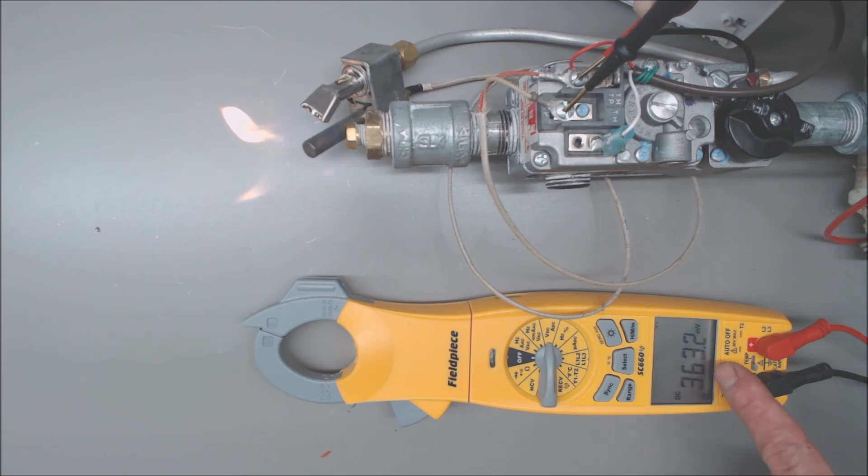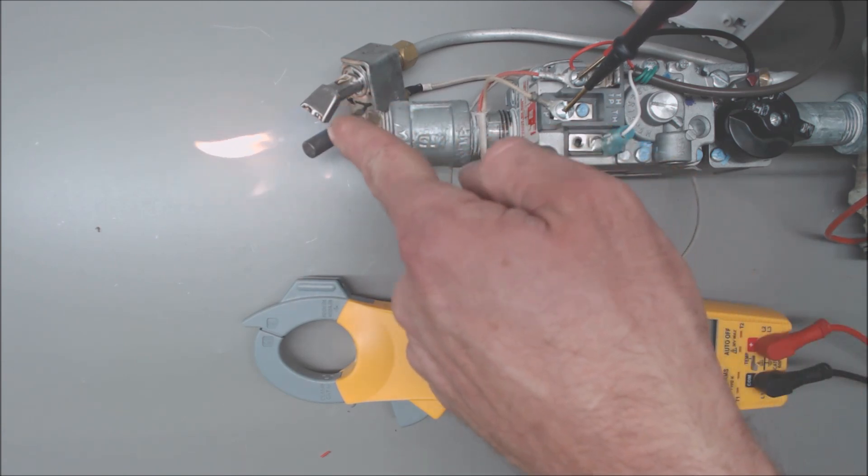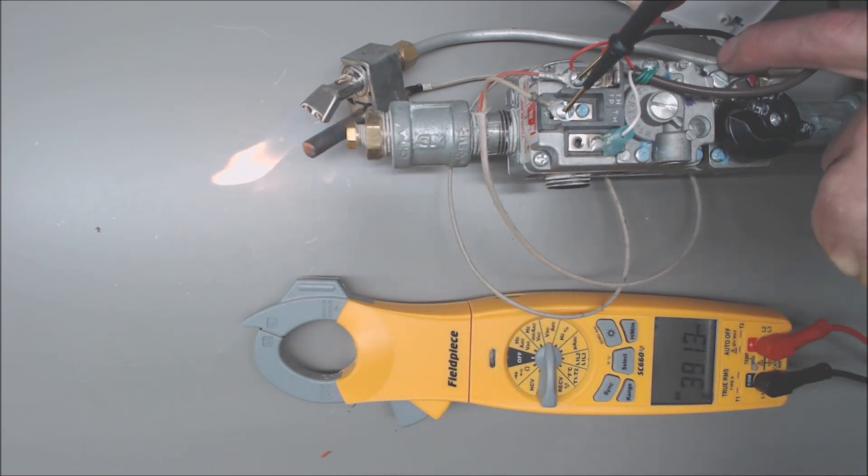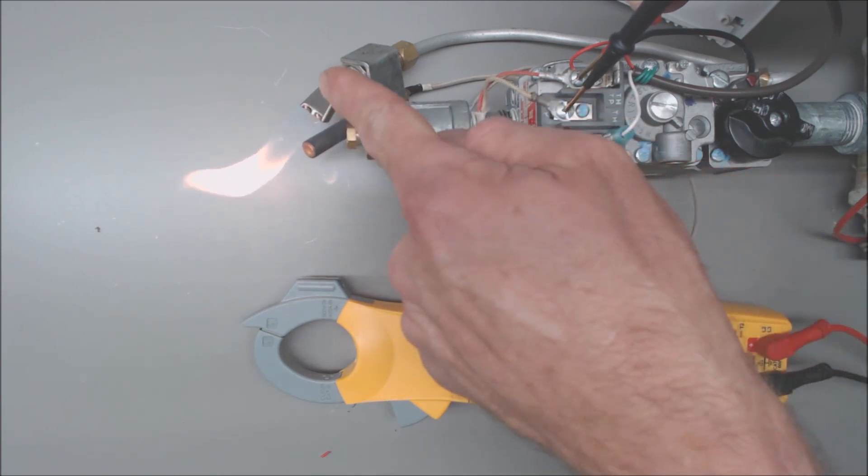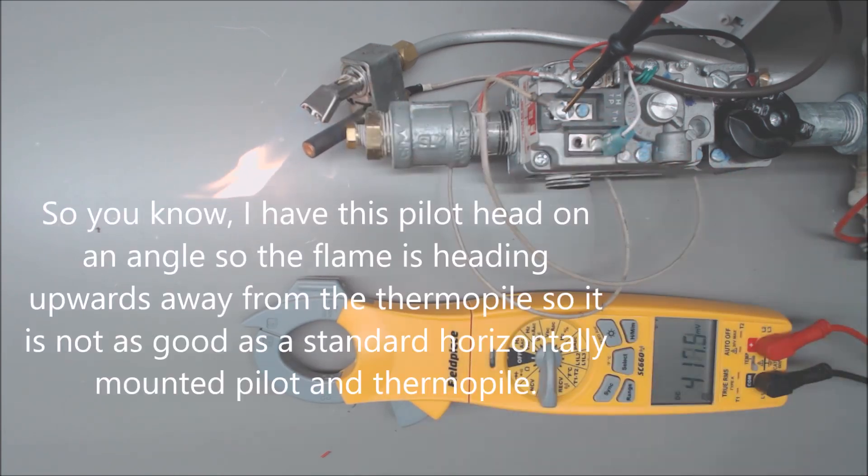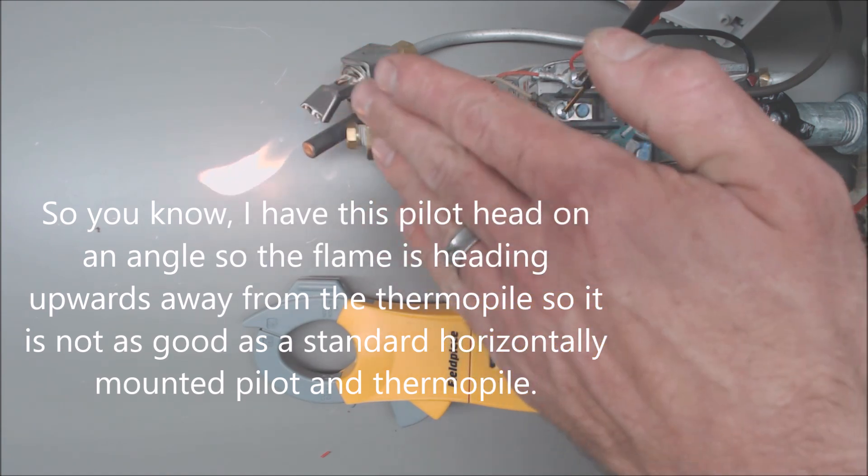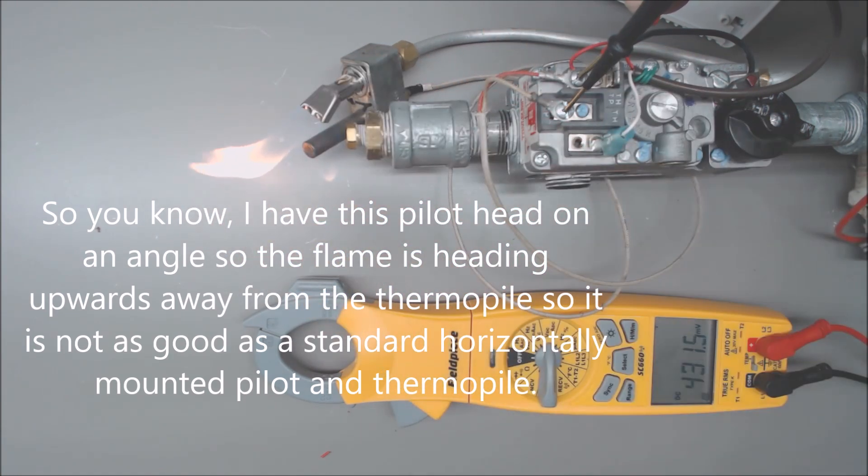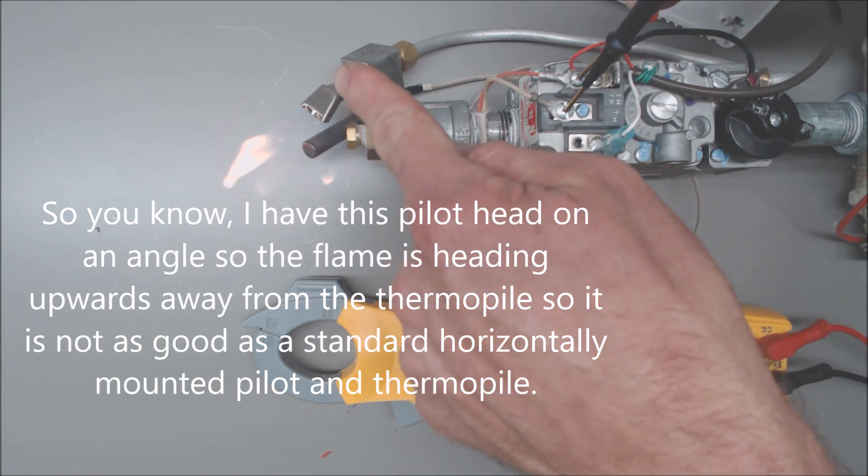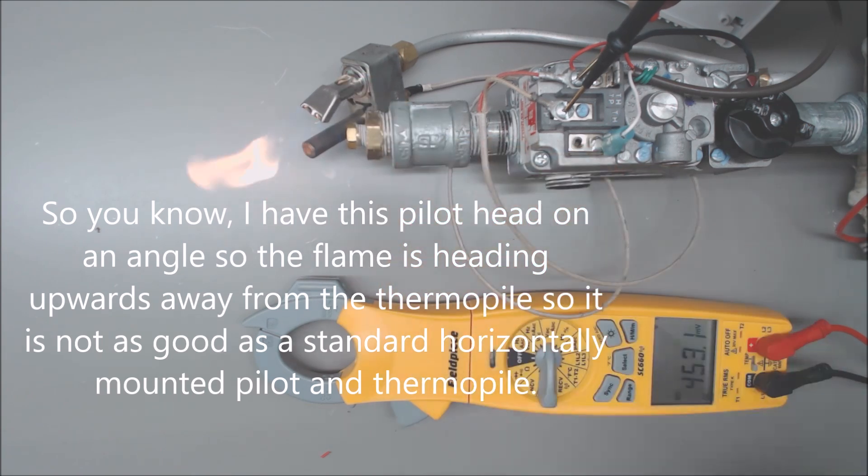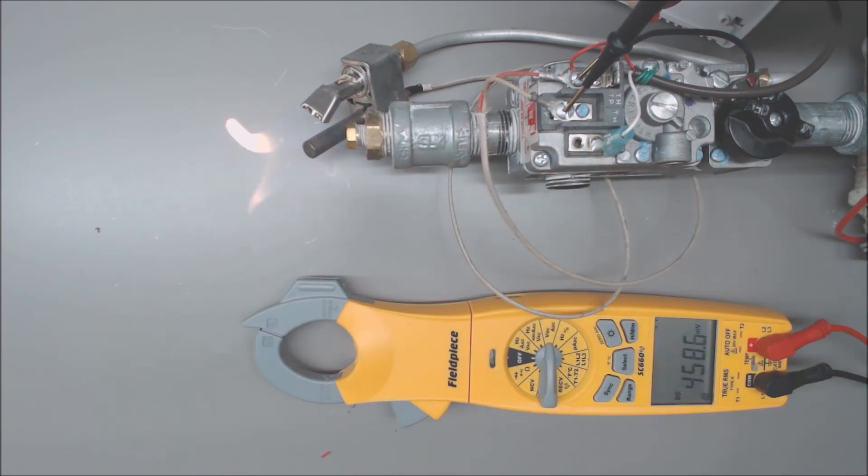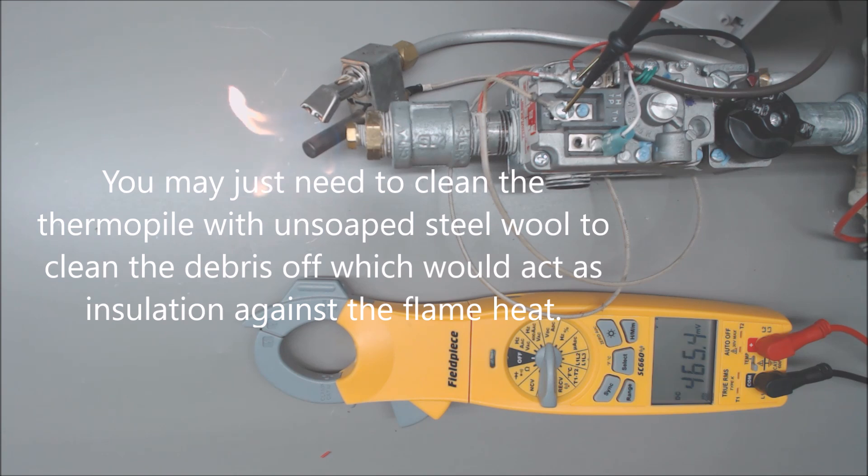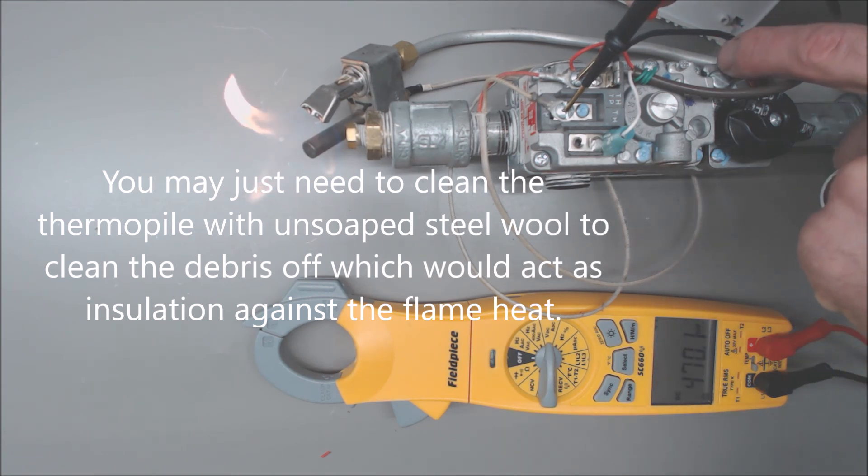If you do have a problem with not getting your millivolt reading up high enough, you may need to adjust your pilot flame. There's a little screw back here for pilot adjustment. You may need to adjust your flame, or maybe possibly this head is bent out of whack and maybe the flame is coming up too high and it's not really engulfing the thermopile. You may need to either replace that or adjust that pilot head, or you may need to adjust that flame higher.